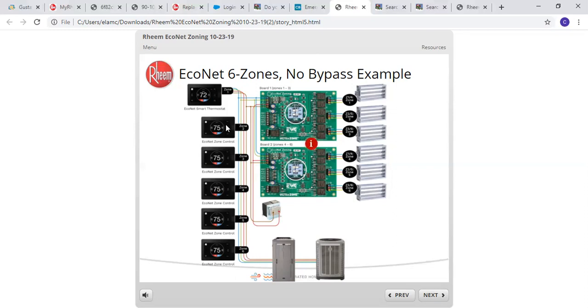In this case, it doesn't really matter what configuration these are staggered in, but you're going to go into 1 zone stat, 4 wires in, 4 wires out. Daisy chain to the next zone stat, 4 wires in, 4 wires out. You're going to daisy chain from one to the other till you hit the end of the line. In this case, they're using the example zone 1.